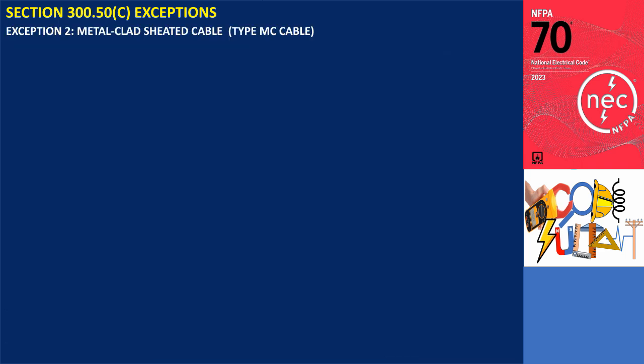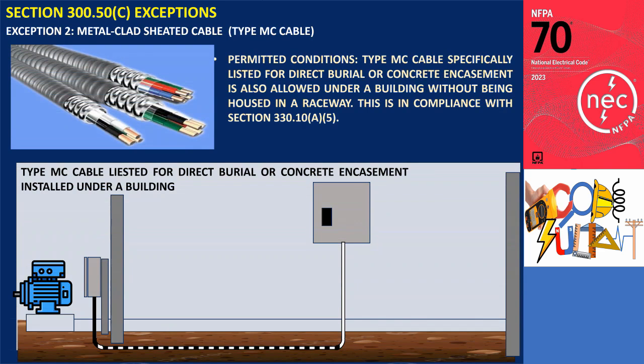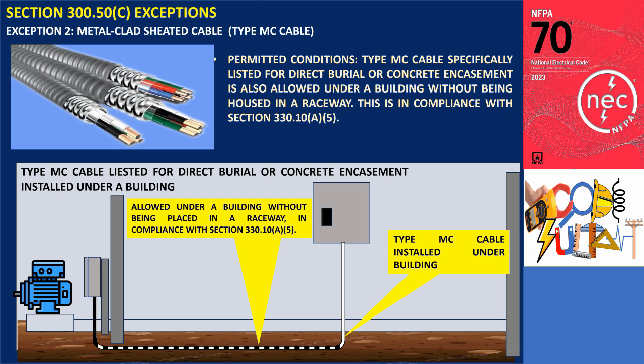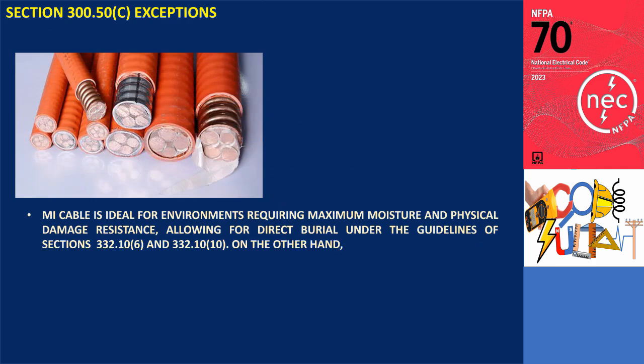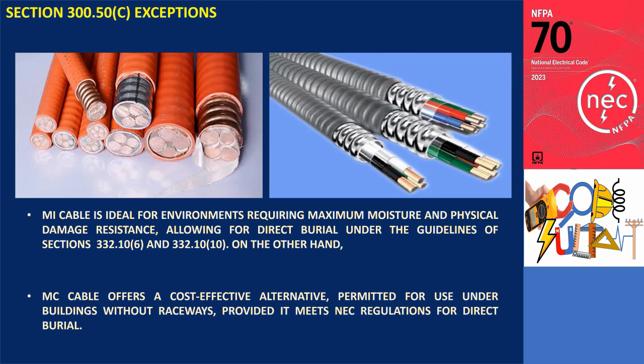Exception No. 2: Type MC Cable. Type MC Cable, specifically designed for direct burial or concrete encasement, is also allowed under a building without being placed in a raceway, in compliance with Section 330.10(A)(5). MI Cable is ideal for environments requiring maximum moisture and physical damage resistance, allowing for direct burial under the guidelines of Section 300.5. On the other hand, MC Cable offers a cost-effective alternative, permitted for use under buildings without raceways, provided it meets NEC regulations for direct burial.